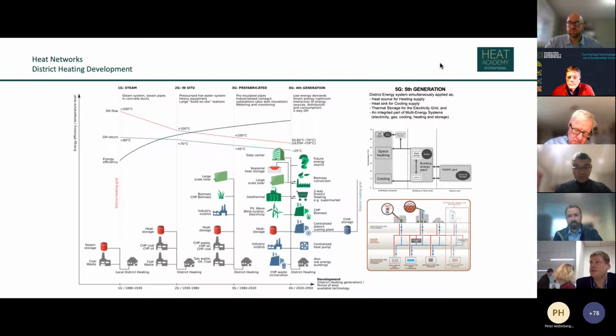In recent years, almost 15 years ago now, time flies, the fourth generation district heating started to develop, with temperature levels coming down to around 60 to 65 degrees. The reason for this is both to reduce heat losses, since we increase efficiency, and also to utilize more excess heat, waste heat, and other low-grade energy sources. This is something we see being developed more and more. Nowadays, the fifth generation is under development, often referred to as one district energy system, working both as a heat source for heating and as a heat sink for cooling purposes.